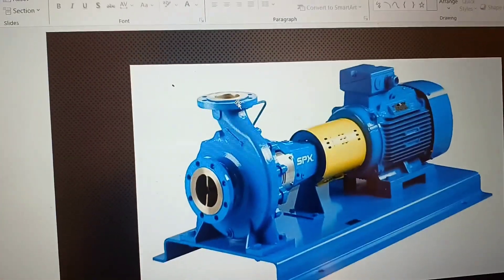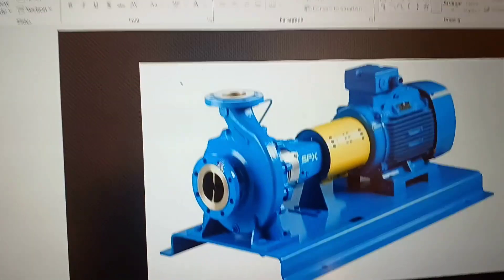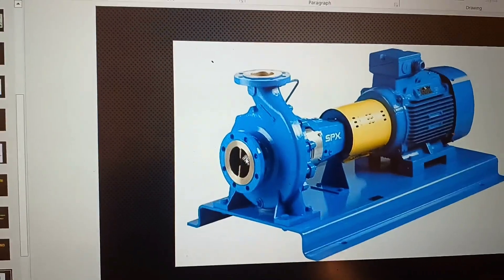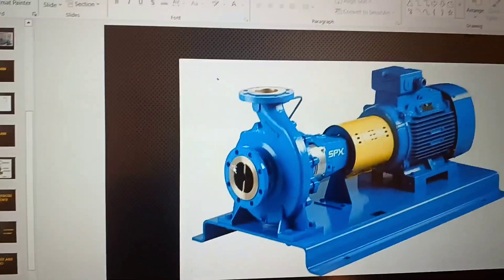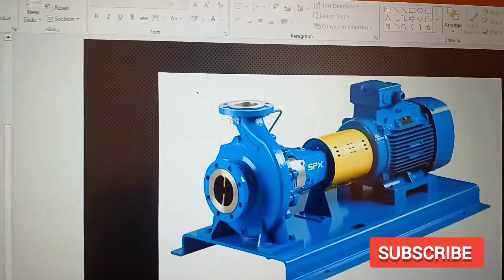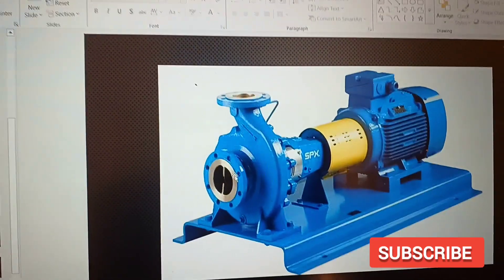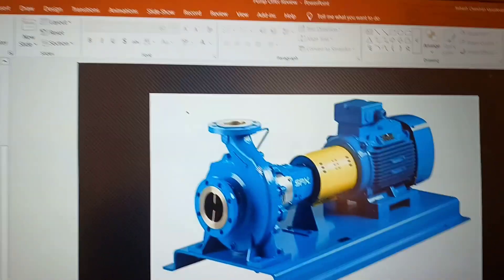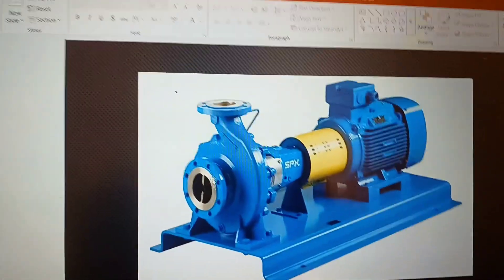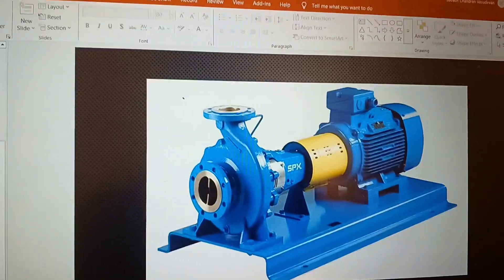The seventh point is to verify the nozzle size and rating. This is where you connect your piping to the pump nozzles — suction and discharge. You need to know the sizes of the suction and discharge nozzles, as there may be a size difference between them. The vendor must provide this information separately, clearly classifying which is the suction line and which is the discharge line.